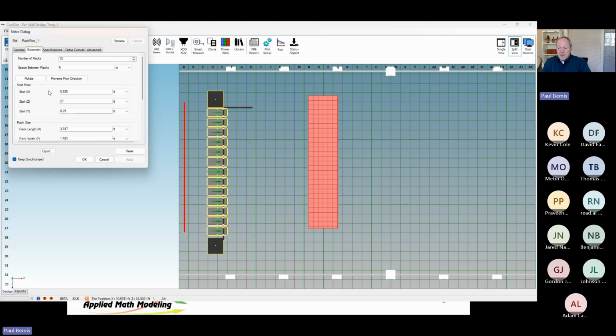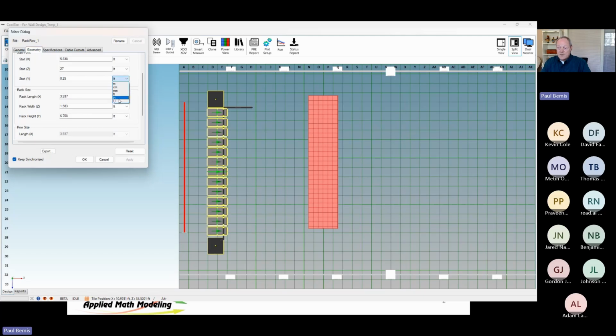All I have to do is pick the rack size and then put the quantity in and then put the gap between racks in. You see, I have it up off the floor by, in this case, 3 inches. I have the length of the rack can stay whatever it is. It doesn't matter so much there. You see, I've got the rack at 19 inches wide, and I've got the height at 80.5, which we have a U figure here is 46 U's. I want to represent all the U's. Remember, I'm really modeling servers here. So this is a 46U rack. I got 46 slots in it.